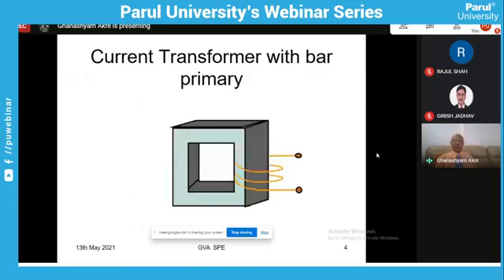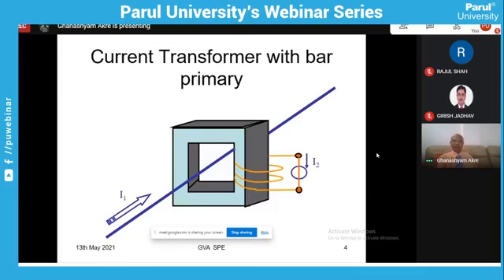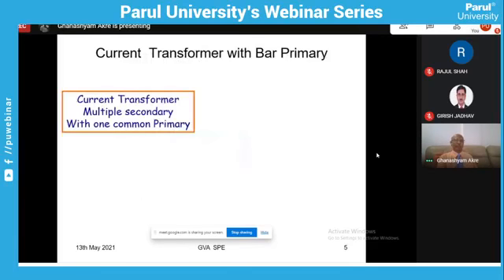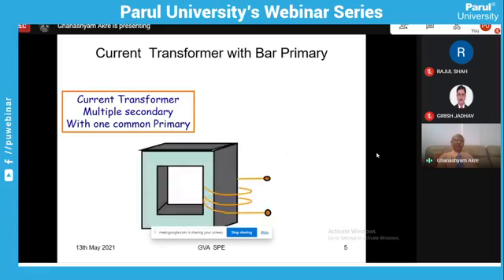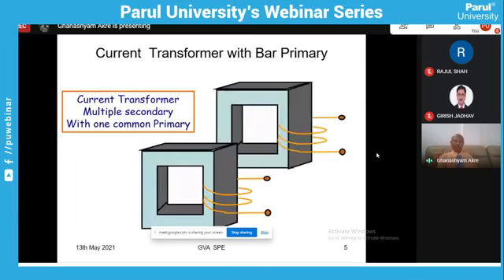Now there are different current transformers. There is a core. This is the primary. These are the secondaries and the secondary load. Similarly, this current transformer can have multiple secondaries. That means one transformer has one secondary, a second transformer has a secondary, and both these transformer cores are looped through one common primary. So this is also possible. That means one common primary and two secondary cores here, but they can be more. I will explain afterwards why you require more secondaries across this.